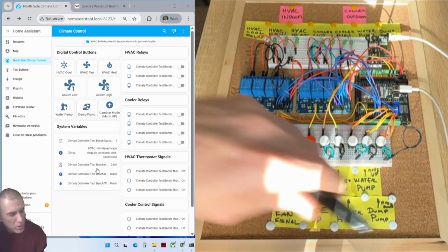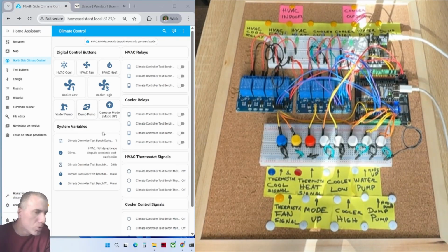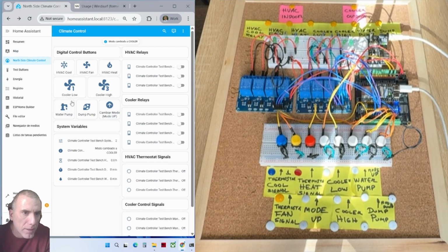Now we will change the operational mode to number 2, which is evaporative cooling, and here we can test the cooler low signal. You see that we have a delay here between the water pump and the fan of the cooler low signal. If I press the other signal, that is cooler high, we have an interlock, and we have the delay as well in between the water pump and the high fan speed.